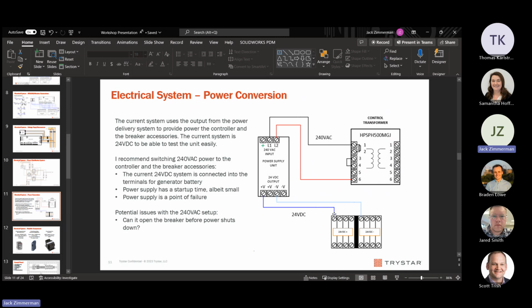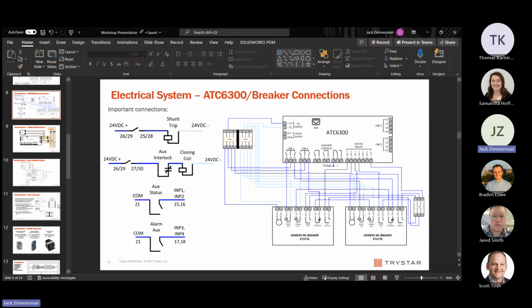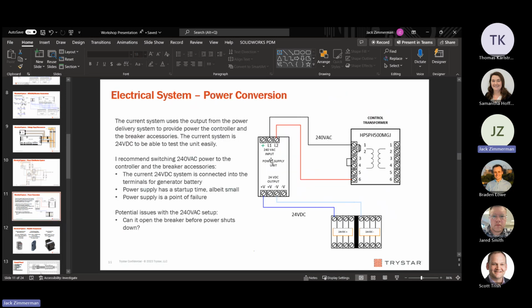And 240 volt power, which we could do for the entire control system. For all of this, we could do 240 volt power. But I think if I was doing this again, I would recommend switching to 240 volt AC power for the controller and the breaker accessories. And there's a couple of reasons for this. For one, the current 24 volt DC system is connected to the terminals on this controller that is typically used to connect a genset battery to it. And that's okay, because that's the only 24 volt DC connection.